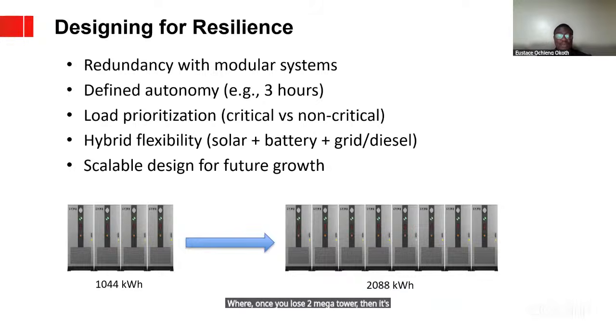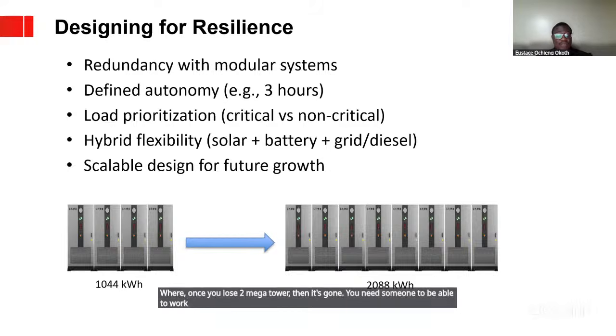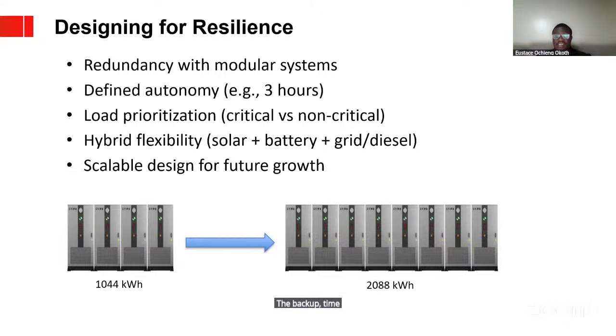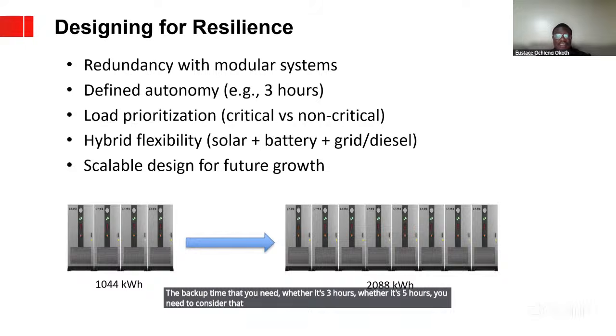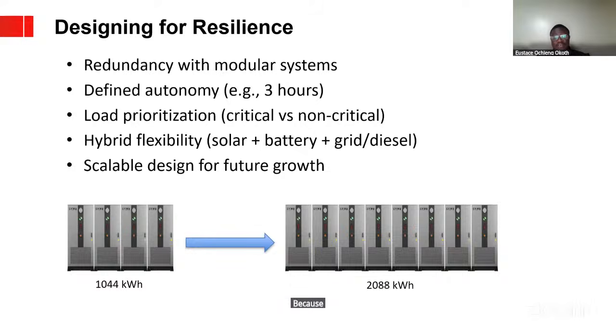You need someone to be able to work on it, to be able to revive its operation. The other thing that when I look at resilient design, look at the backup time that you need, whether it's 3 hours, whether it's 5 hours, you need to consider that. And in considering the backup time, you also need to consider the load prioritization. That means you need to define what a critical load is and what is an uncritical load, because this helps a lot in also reducing the cost of the project generally, because battery is still very expensive.